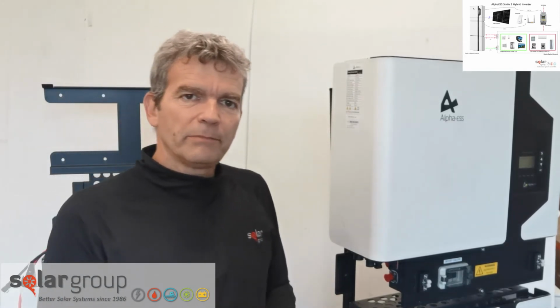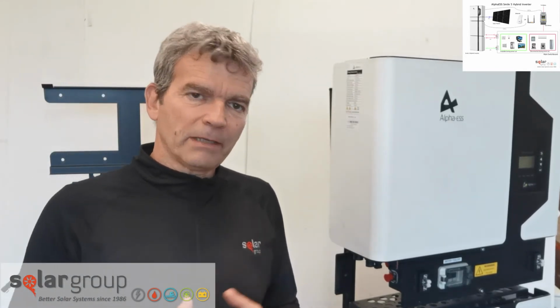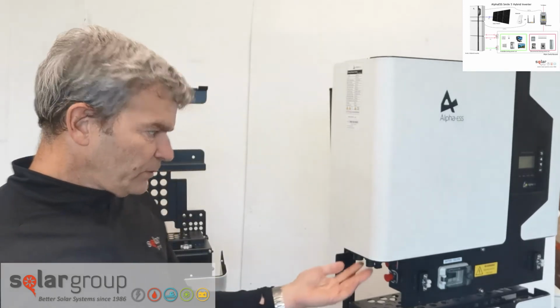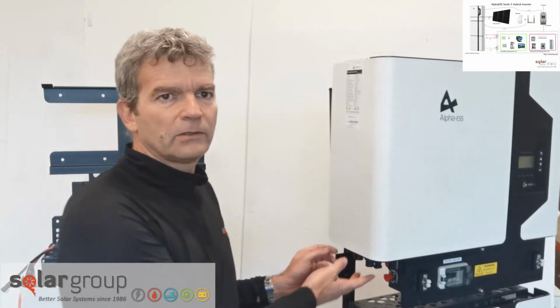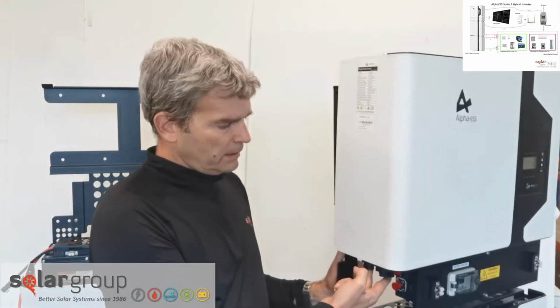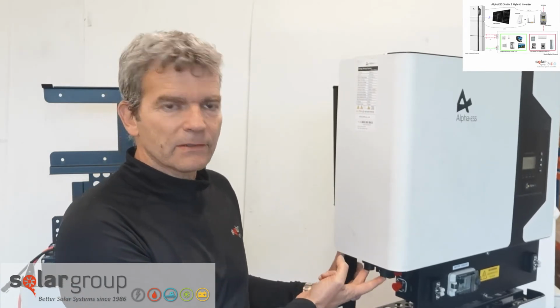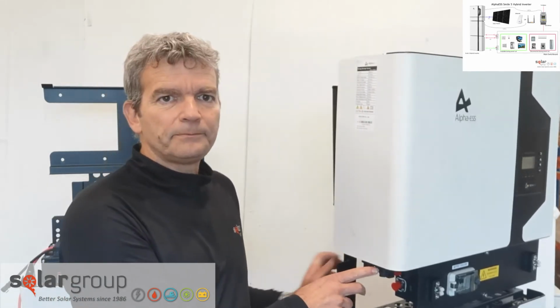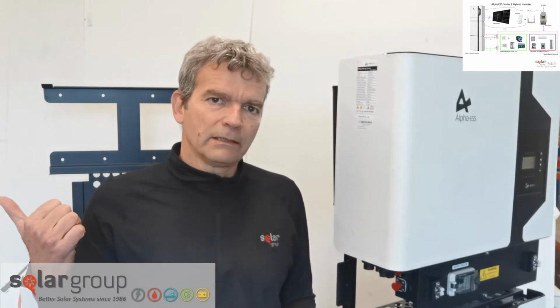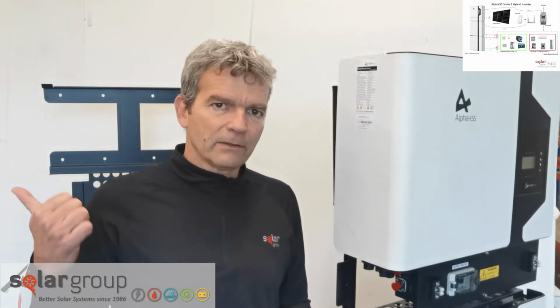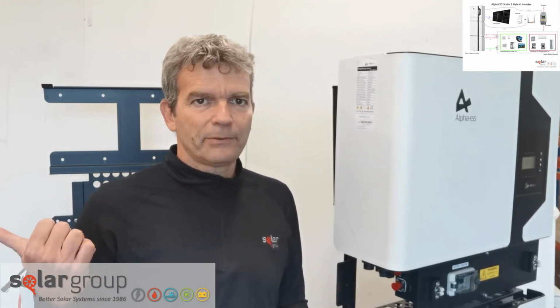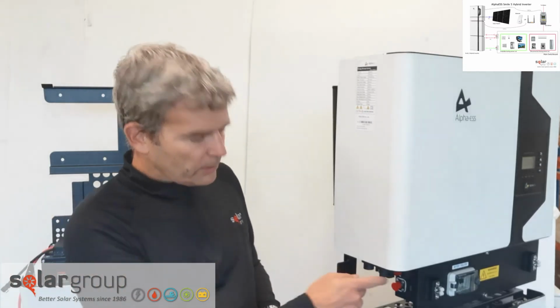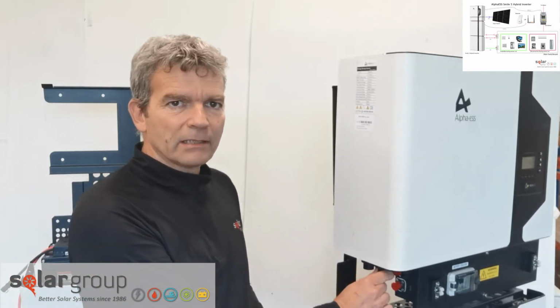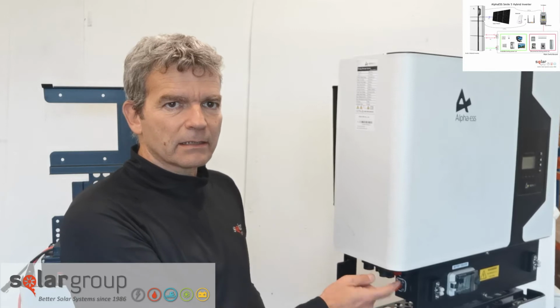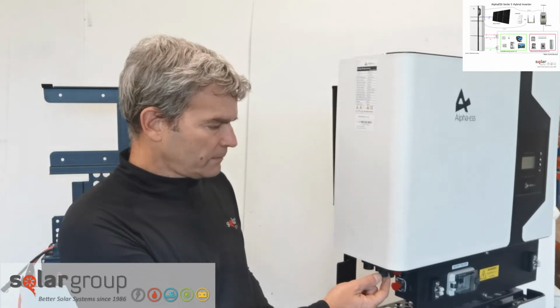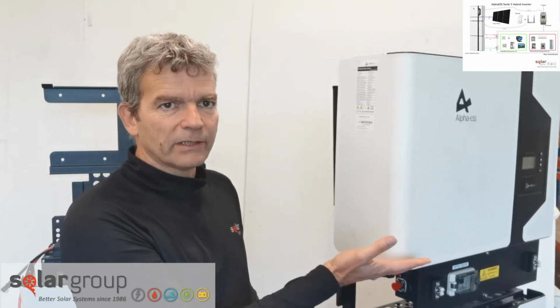So, battery cabling we spoke about. Let's talk about AC. We have two AC connections here, two plugs that are pretty common with inverters. This one is the grid. You need to get a 4mm cable with a 25 amp circuit breaker, connect it here, and basically this is going to get the grid connected and the inverter can work.